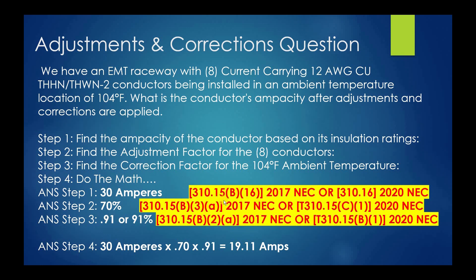A couple of keynotes on code references. For ampacities, it's table 310.15(B)(16) in the 2017 code; in the 2020 code it goes to 310.16. For adjustment factors — number of current-carrying conductors in excess of three — it's 310.15(B)(3)(a) in the 2017 code; in the 2020 code that changes to table 310.15(C)(1). For the correction factor for ambient temperature, it's 310.15(B)(2)(a) in the 2017 code; in 2020 it goes to table 310.15(B)(1).